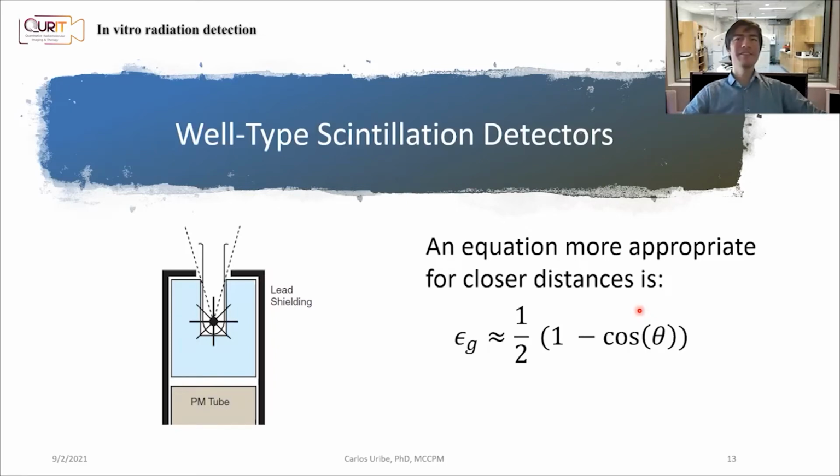You have a detector with a hole in it, and you're able to place your source inside the detector. Think of the dose calibrator we talked about, which is what we call a well chamber. It had gas in these regions, where ionizing radiation creates ions in that gas, and we measure an electric pulse.